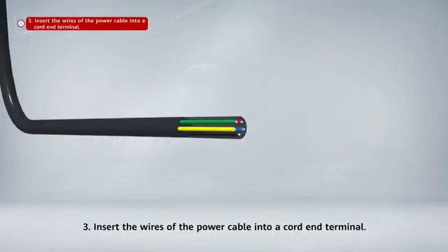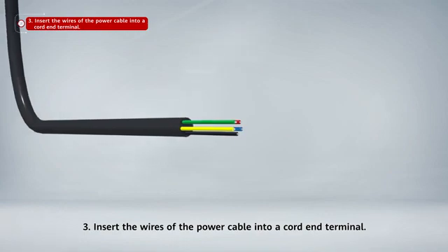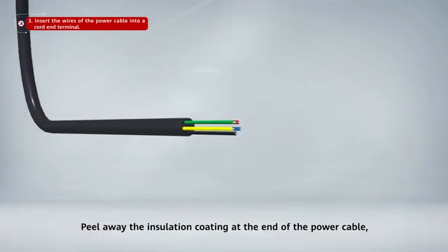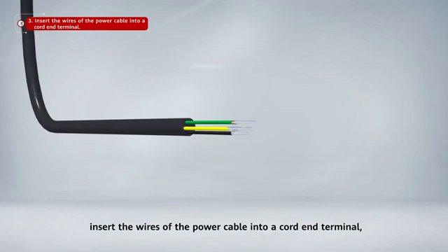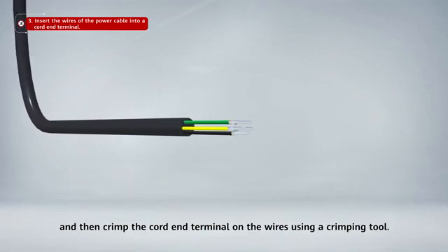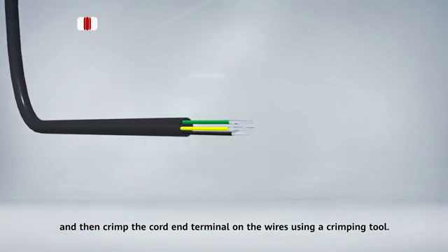3. Insert the wires of the power cable into a cord end terminal. Peel away the insulation coating at the end of the power cable. Insert the wires of the power cable into a cord end terminal, and then crimp the cord end terminal on the wires using a crimping tool.